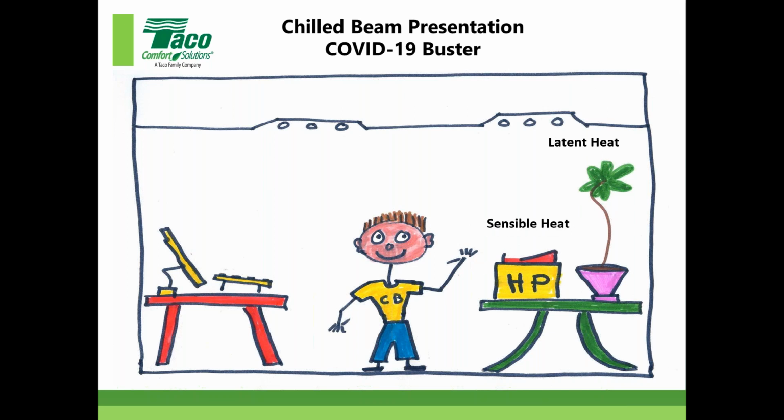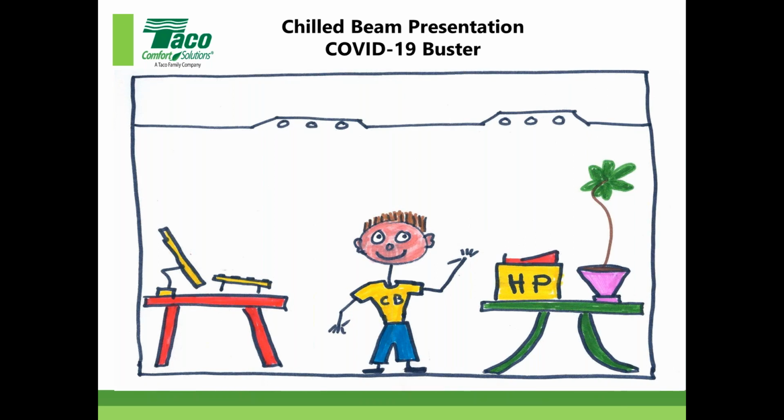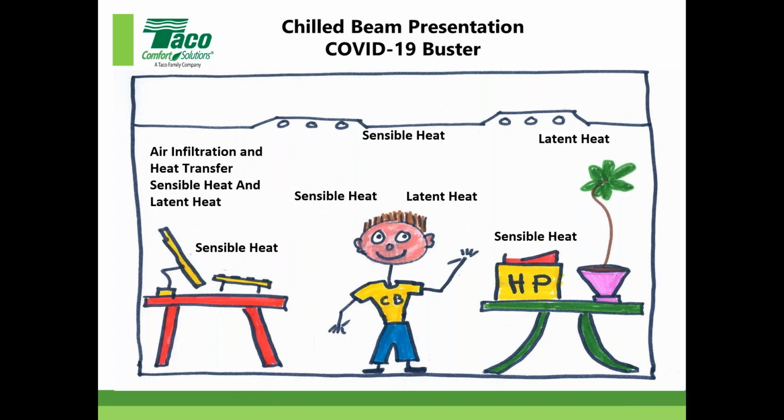Now there's a trend building here. You'll see that the majority of items that I've called out add sensible heat, and then we have a minority grouping that add latent heat. As it turns out, if we do a complete inventory, including the people in the space and the outside air, it turns out about 80% of the heat that's added to the space is sensible heat, and about 20% is latent heat.